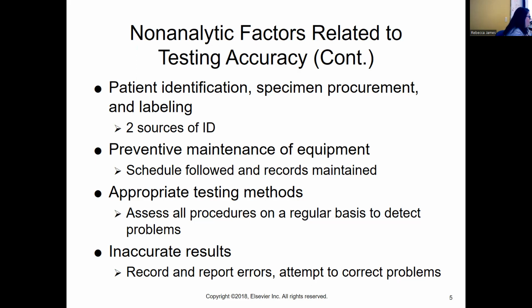Sometimes you have monthly maintenance. So with that instrument, you have a monthly maintenance that you have to do, and that's cleaning the inside of the instrument. You have to run a clot preventative up in it and a bunch of other stuff. You have to do that every month to make sure that that instrument is kept in the best working condition. Sometimes you might have 6-month maintenance on an instrument. Six-month maintenance might be changing probes or changing out different parts.